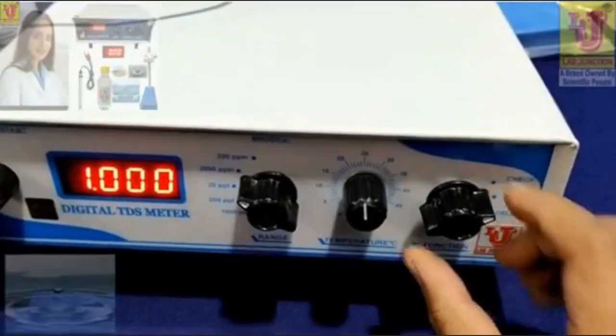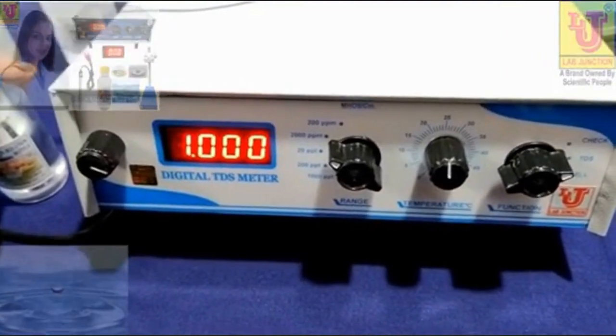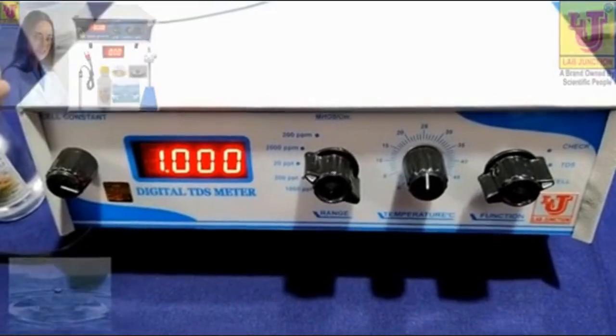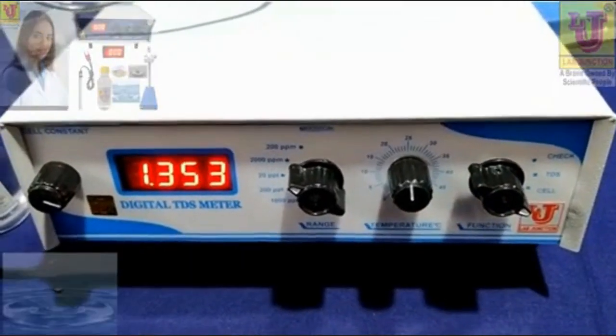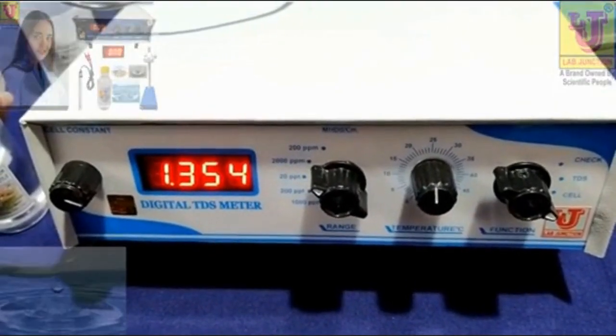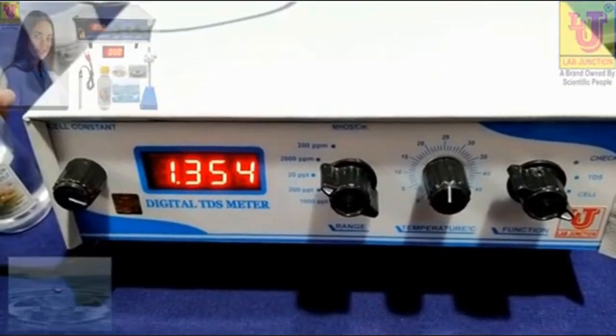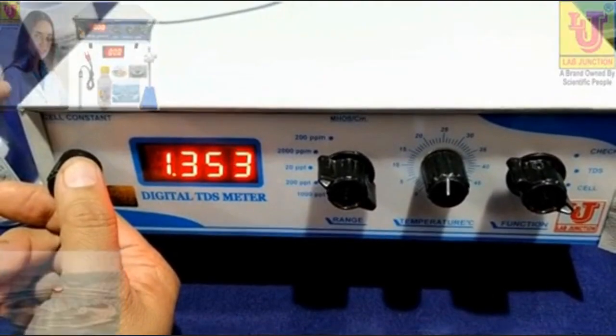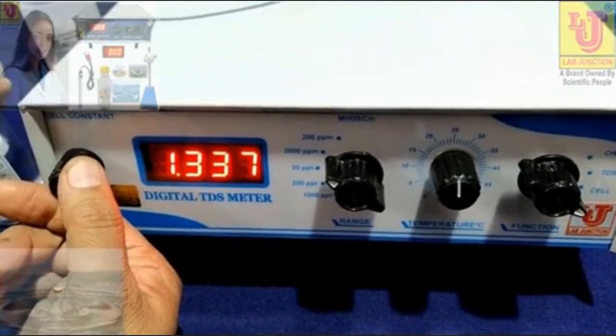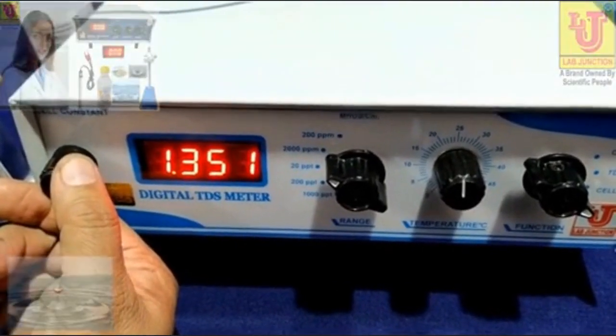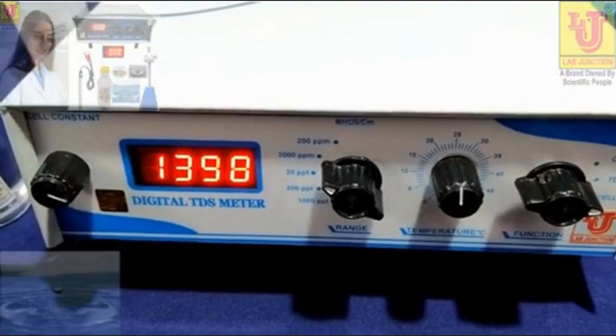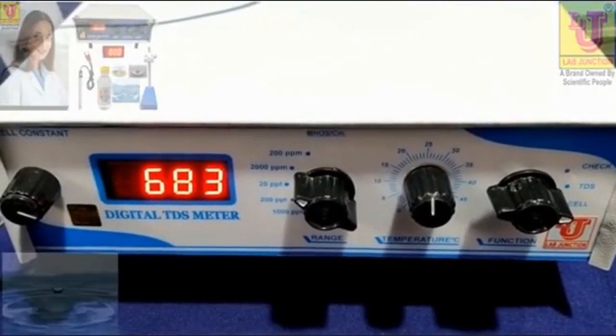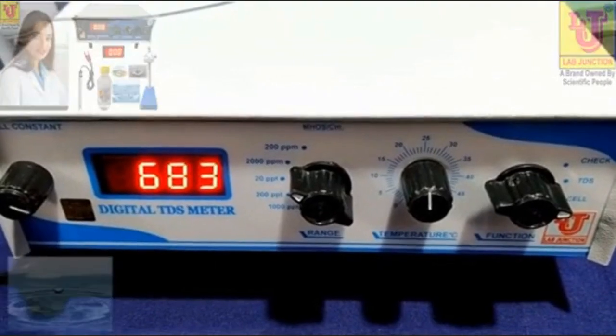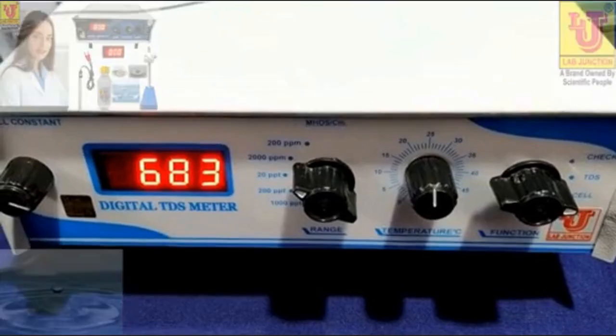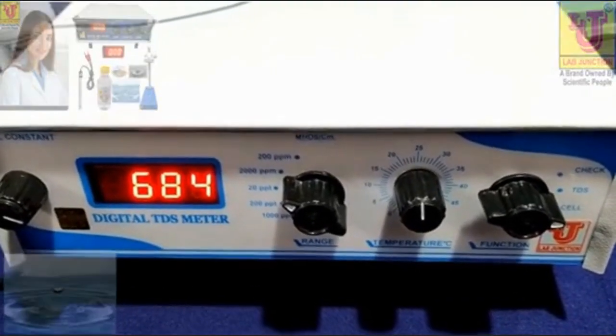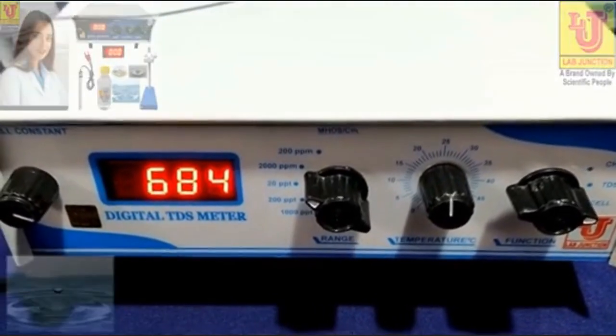then you go directly and you don't have standard solution. You want to calibrate without standard solution, then directly go to cell constant knob. Then feed your standard value. Suppose your standard value is 1.352. Then set from this 1.352. Like this, and directly go to TDS control and take your readings of samples and note down in your notebook. This is the final testing procedure of digital TDS meter. Thanks.